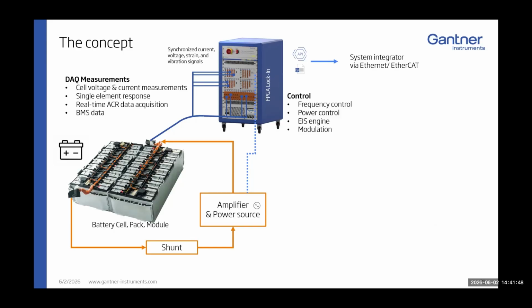On top of that we modulate an AC signal, and we try to measure that AC signal, which is very small. For example, if you apply 5 amps with 1 amp of AC current, the voltage response is in the range of 1 or 2 millivolts. Now imagine a very large battery pack, say an 800 volt battery, and you want to measure that 1 or 2 millivolts — that needs a special data acquisition system that's still synchronized and has all the necessary safety and galvanic isolation.